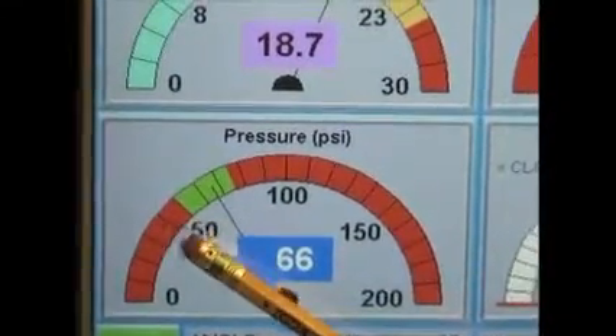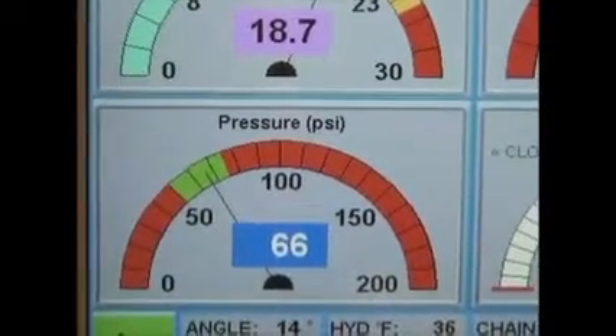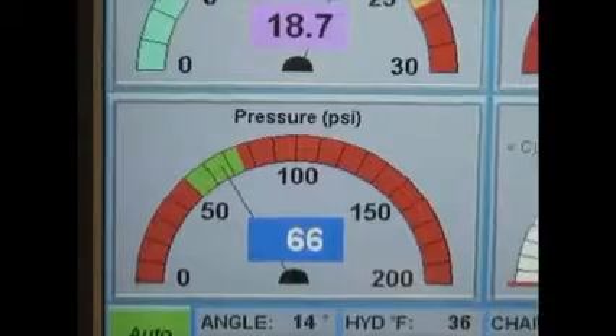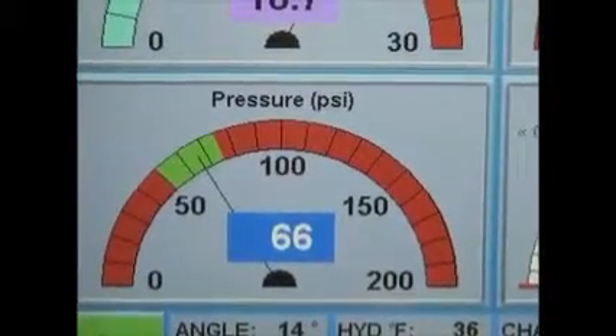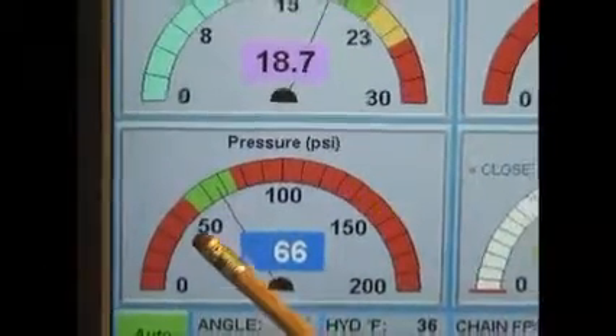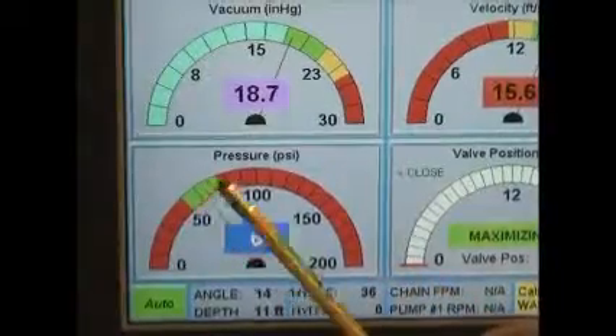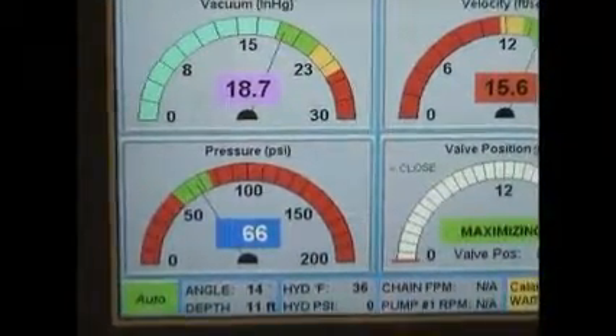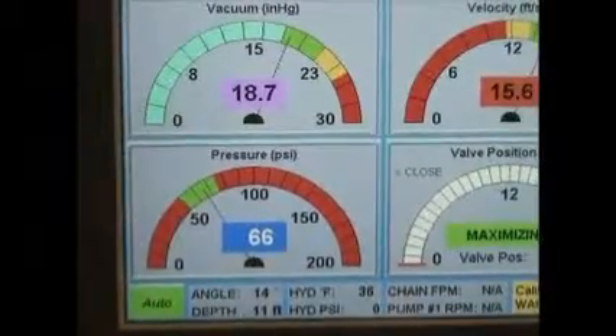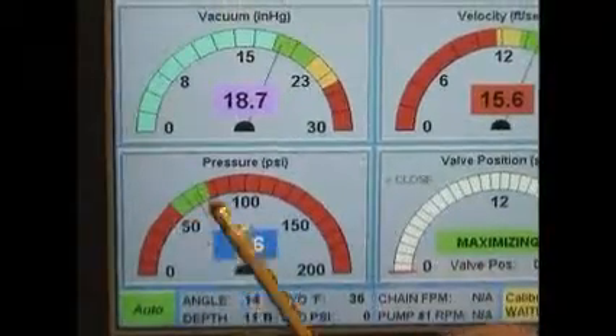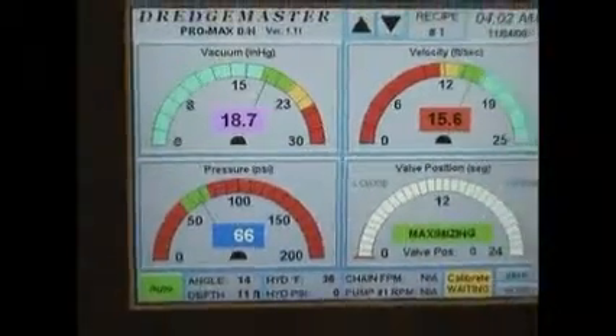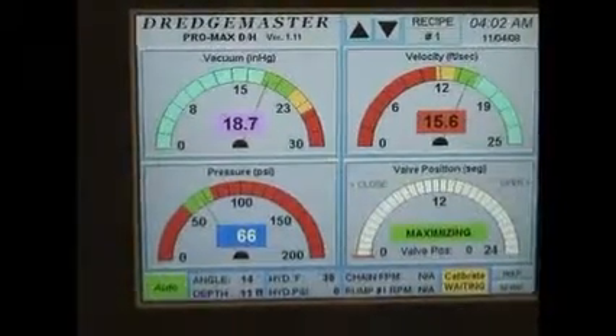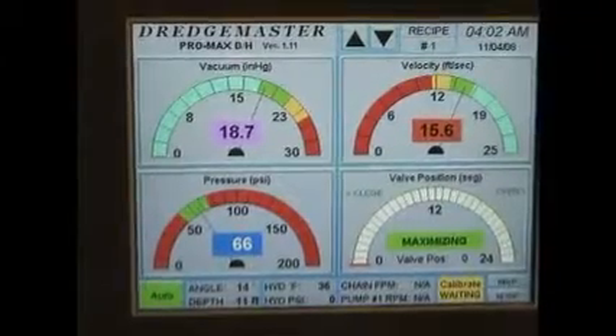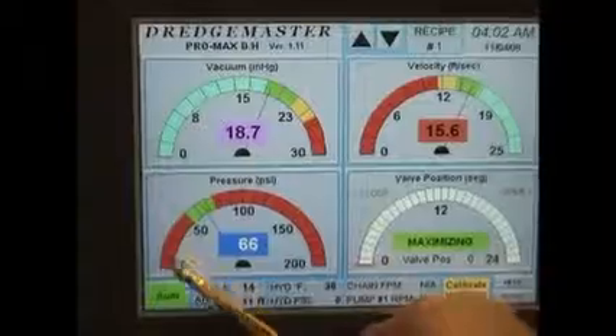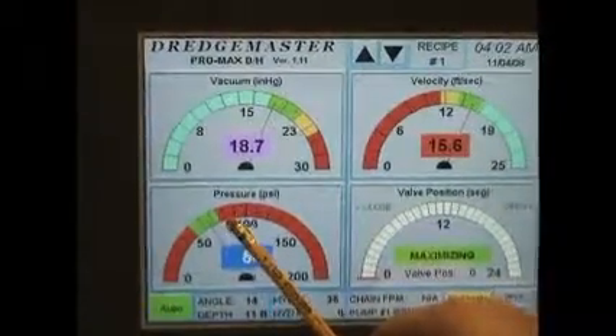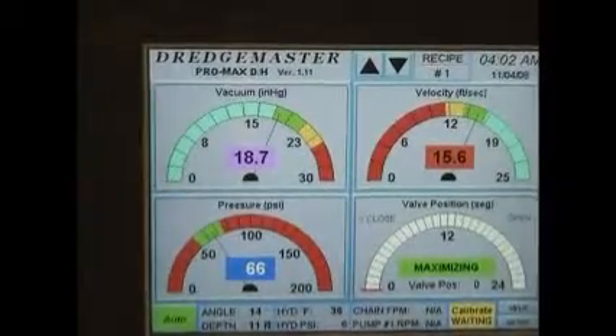If it didn't catch the red zone on the low side, once the material catches hold inside the impeller again, it usually all of a sudden tries to discharge a bunch of material out the discharge of the pipe. When this happens, all of a sudden the pressure will spike up. When the pressure spikes up, we're going to experience a high discharge line pressure. And when that high discharge line pressure occurs, then we will definitely open up the valve on the high side. So it's important to set this green zone in areas where your normal pipeline discharge line pressure or bar is going to be running. And then if you do experience a cavitation issue, we want it to be able to catch it hopefully on the low side first. If not, we want to be able to catch it on the upper side, in the upper red zone.